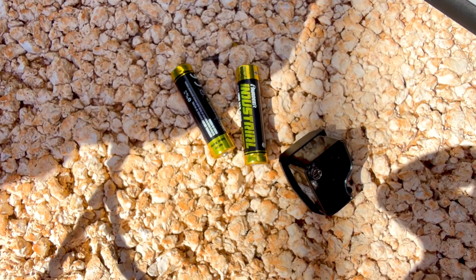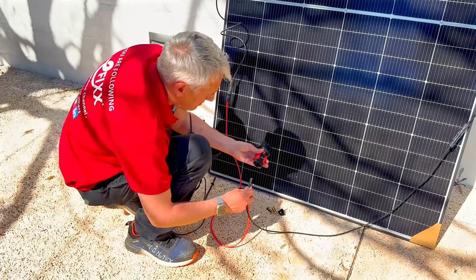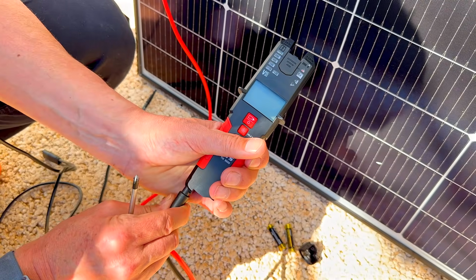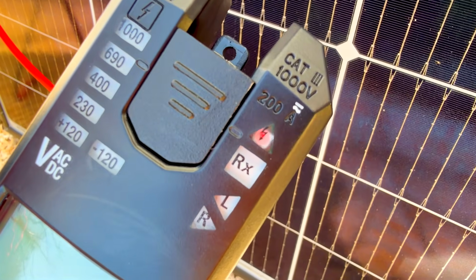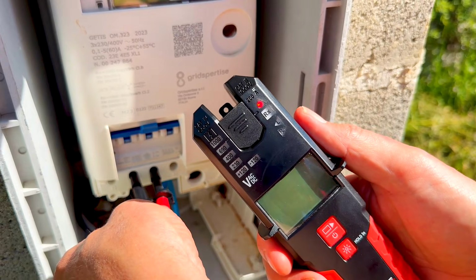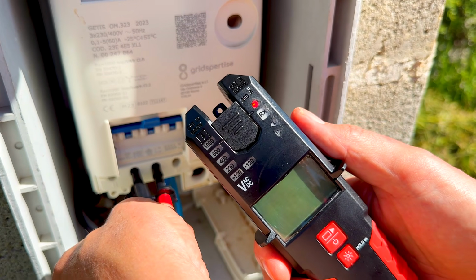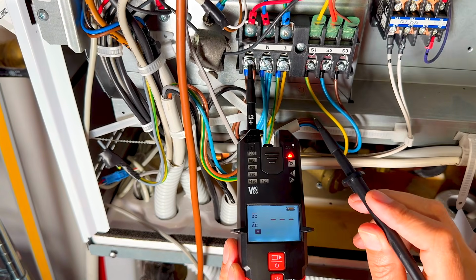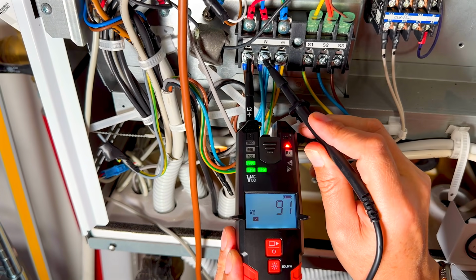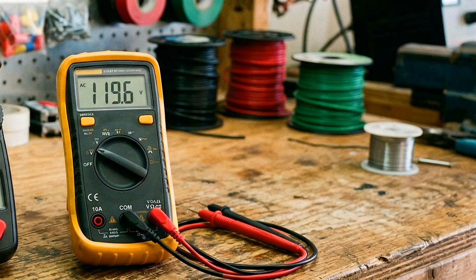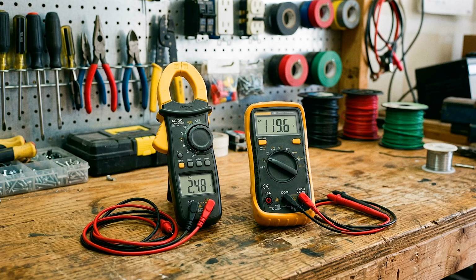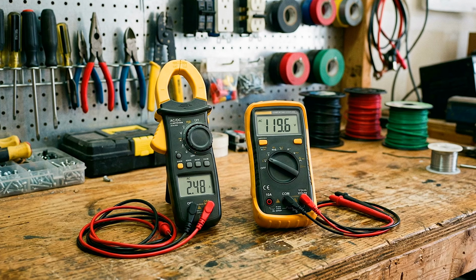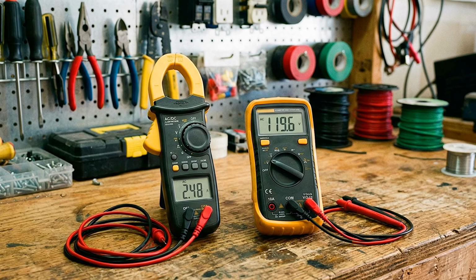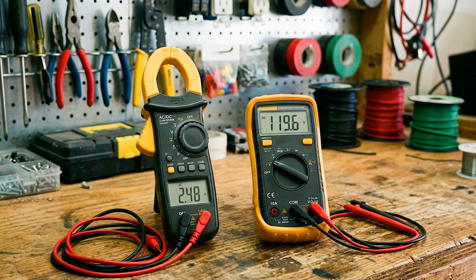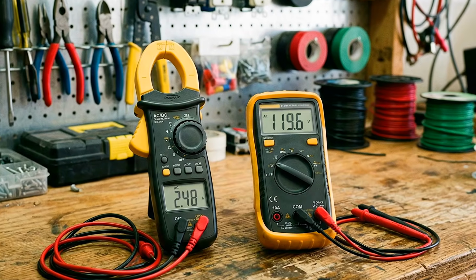So I'm going to try that by removing the batteries just to see if it works on both DC and AC. So DC works even down at 50 volts. Now let's try AC. Again, no battery in there. If voltage is present, it will automatically indicate it, whatever mode you're in, and that's a big difference. With a multimeter or even a clamp meter, which many assume is a safe option, you're depending on that selector dial being set correctly. Get that wrong, and you could be looking at a false reading, thinking it's safe when it isn't.